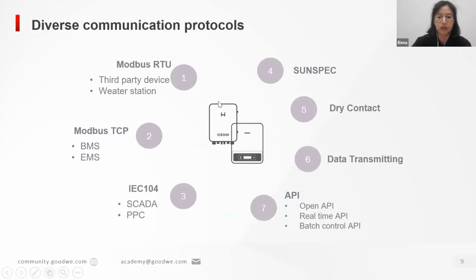So for the different applications, we provide diverse communication protocols, such as the basic Modbus RTU protocol for communication with third-party devices, like the weather station. Modbus TCP for BMS, EMS of the energy storage inverter, and our on-grid inverter and the communication box will also support Modbus TCP to realize more TCP/IP communication. And we also support IEC 104 to communicate with utility systems like SCADA and PPC. GoodWe inverters can also support SunSpec standards, so we don't need to adjust the Modbus address.